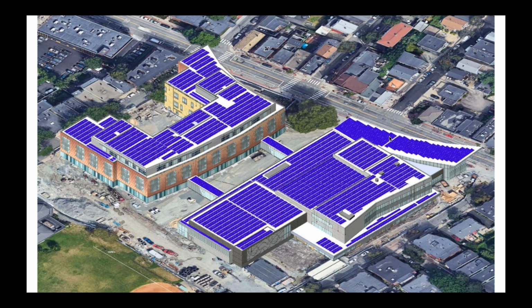In our preliminary layouts, we found we could improve the density of PV panels by going with the east-west layout, minimizing the space removed for panels due to self-shading from panel to panel. The losses we saw per panel for energy generation were exceeded by the additional number of panels we could fit. Since our goal was to maximize energy generation per square foot of roof area, our limiting factor, this orientation turned out to be the most optimal for getting the most energy generation.